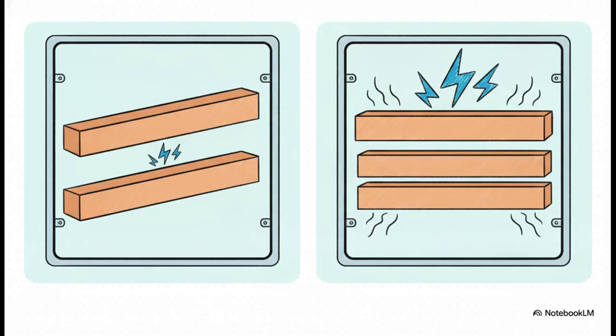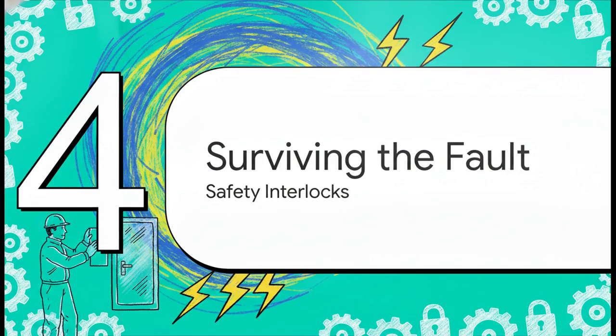Now notice how the physical hardware inside that first compartment scales directly with the current. The busbar compartment is definitely not a one-size-fits-all deal. A standard 1250 amp board typically runs 2 copper busbars per phase, but the second you step up to a 1600 amp rating, boom, you immediately need 3 busbars per phase. The physical copper literally has to scale up so it can carry that extra electrical load without overheating. Which brings us to Section 4, Surviving the Fault and Safety Interlocks.